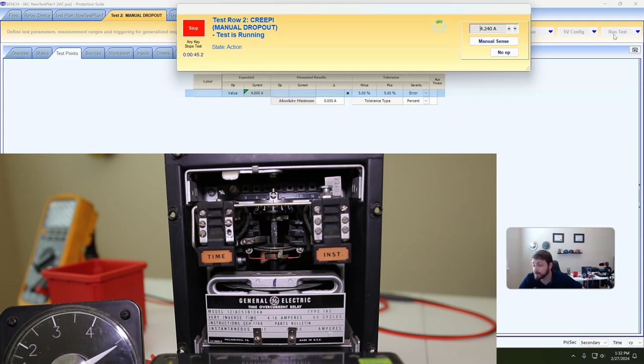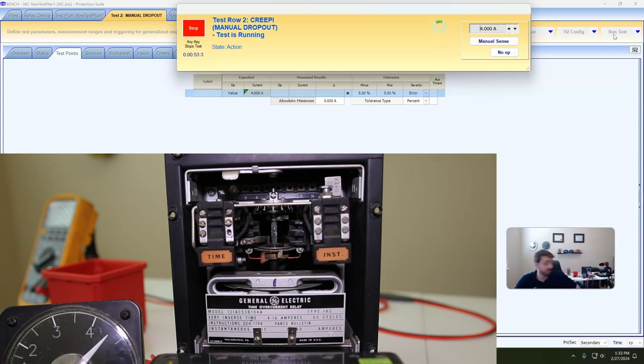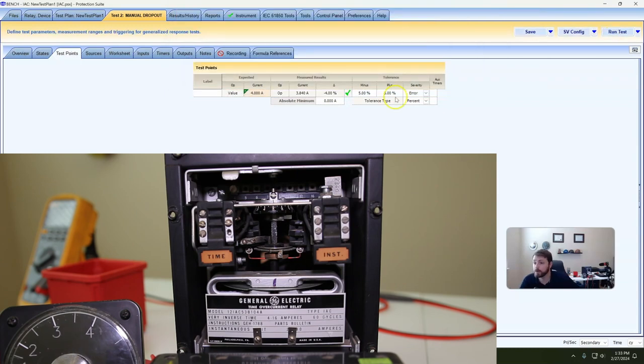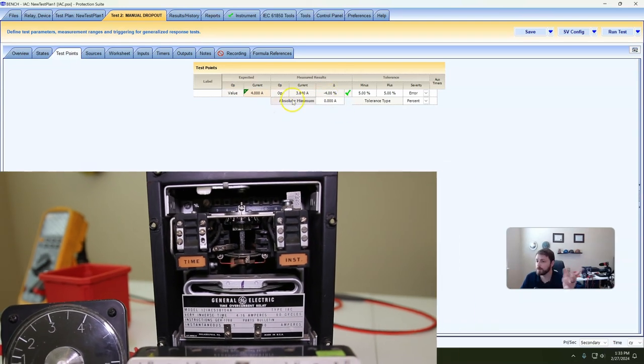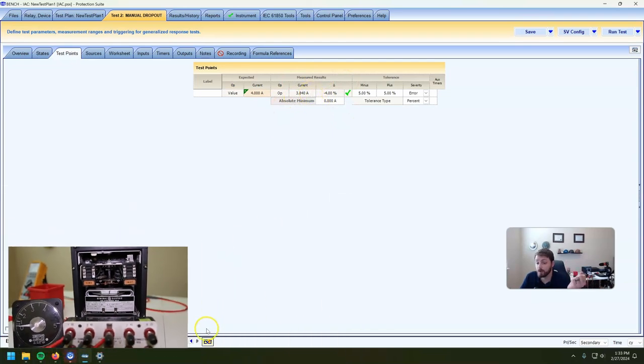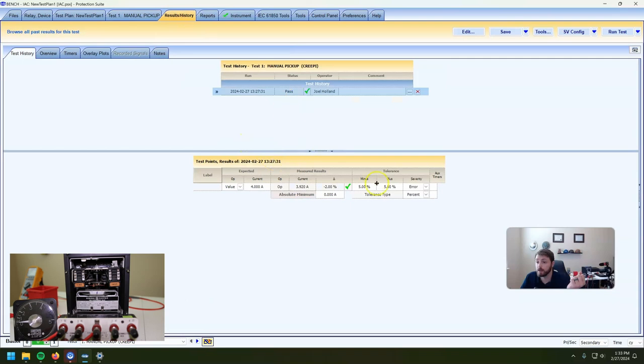Depending on your hardware and software, this might be the easiest way to do it, and it's relatively accurate. Right there we're at four amps — dropped out right at four amps. The seal-in unit requires current through the trip circuit and we don't have that, so it's just that contact on the disc. Our dropout: 3.84. Our manual creep pickup was 3.92. So they're different numbers — it's fairly accurate, but they are different numbers. That is something to be aware of.